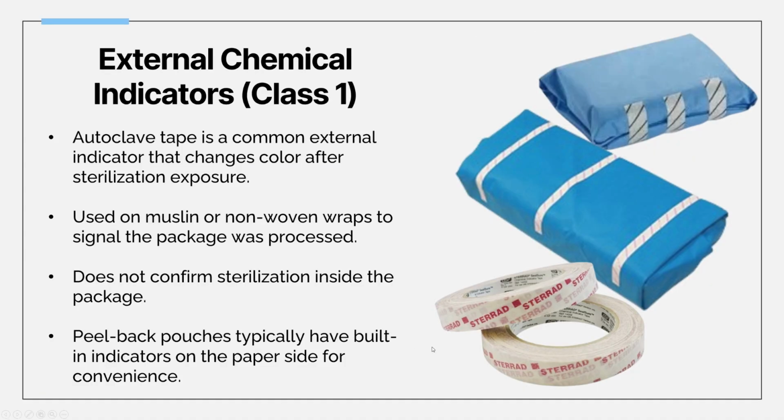But all kinds of sterilization methods actually have different kinds of autoclave tapes that you use. So a typical one is this one, which is the steam. And this one, as you see here, is used for STERRAD. So this will successfully react to hydrogen peroxide sterilization methods. You can't use them interchangeably. So this one has to stay within a STERRAD, maybe even a vPro system. This one cannot be used as a substitute for this method. It just won't work. It will not react at all. It will not change colors.